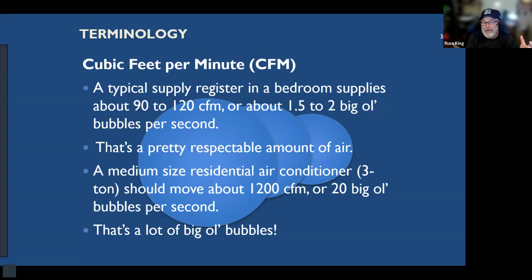5-ton air conditioners, 5 times 400 is 2,000 CFM. That's what they're designed for. That's what they're supposed to move. Now, the question is, did they size the ducts correctly to allow that many bubbles to pass through the duct system? And that's where things start to fall apart, because they don't.